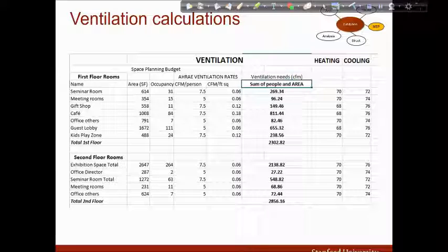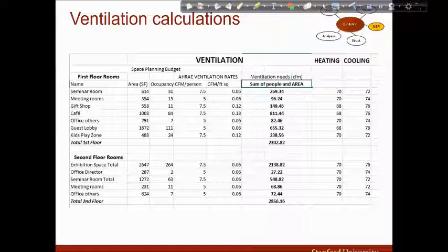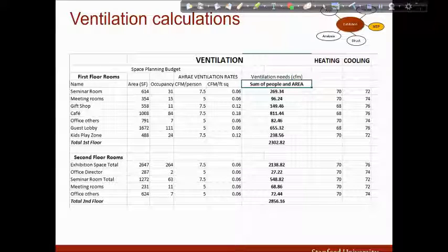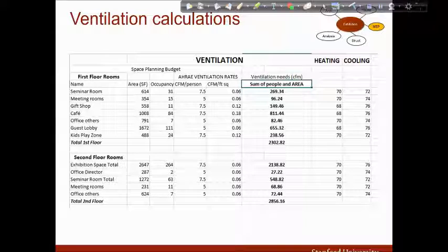ASHRAE has published the required CFM per person and per square foot. I calculated the total ventilation needs taking into account the area and the occupancy of each room, and used the size duct tool to size the ducts in order to provide that amount of ventilation. The heating temperature is set to 70 degrees Fahrenheit in all rooms apart from the welcome lobby zone in which it is set to 68. The cooling temperature varies from 72 to 76 depending on the use of each room.